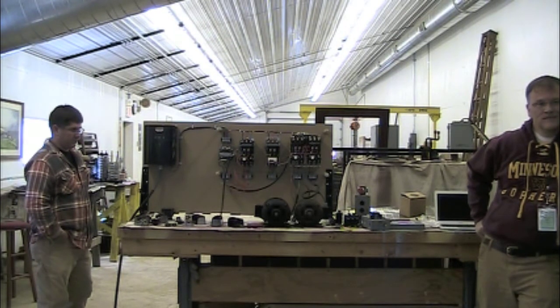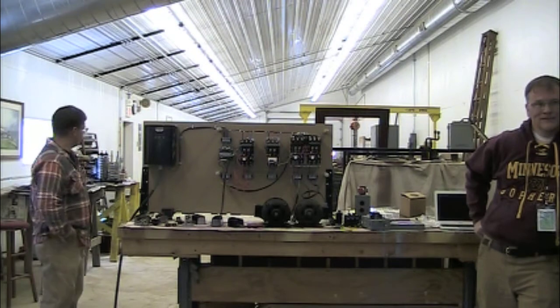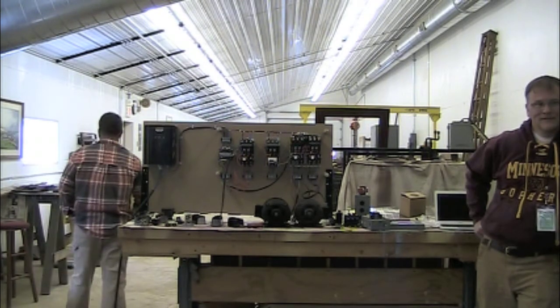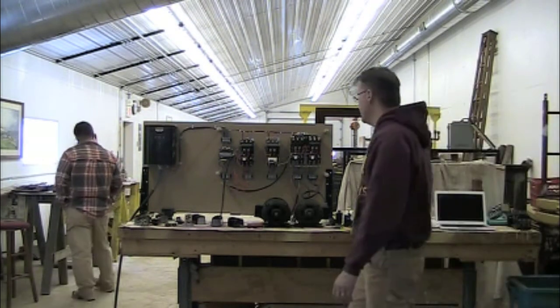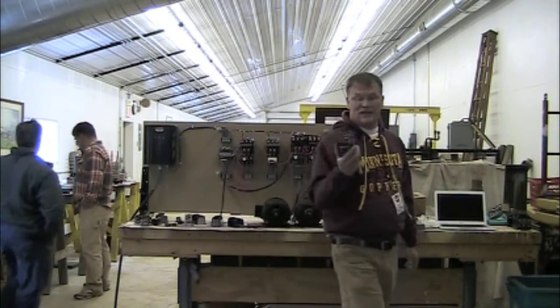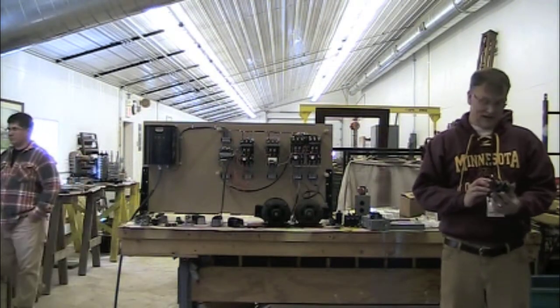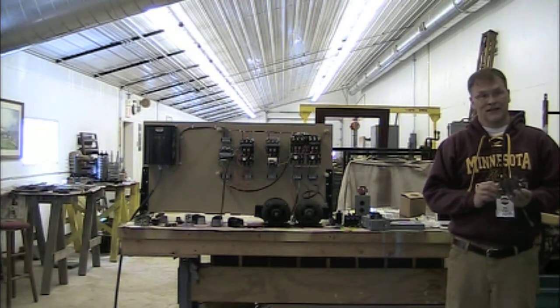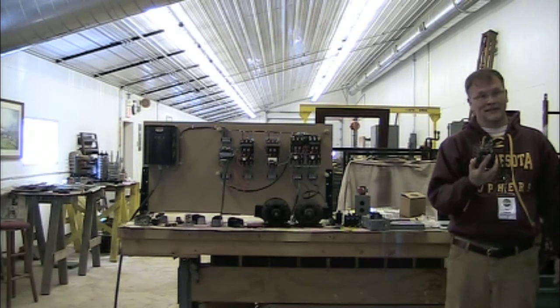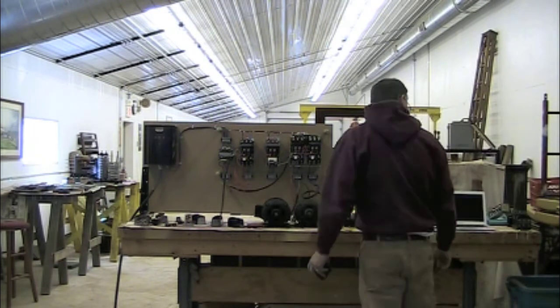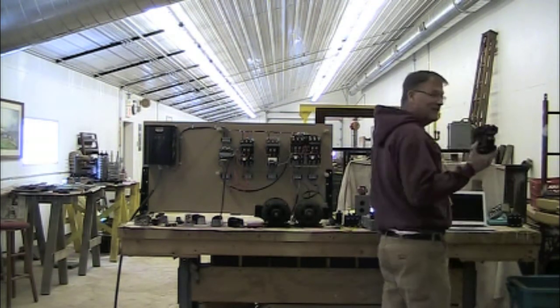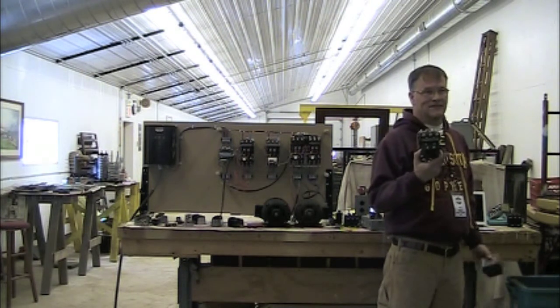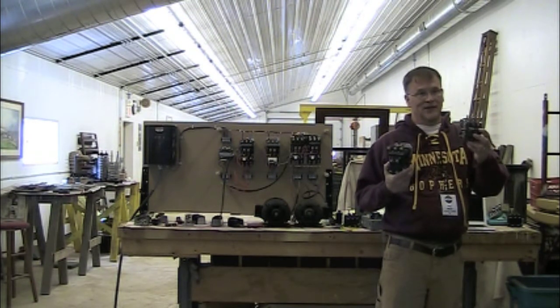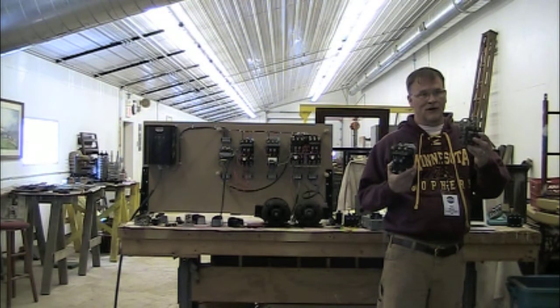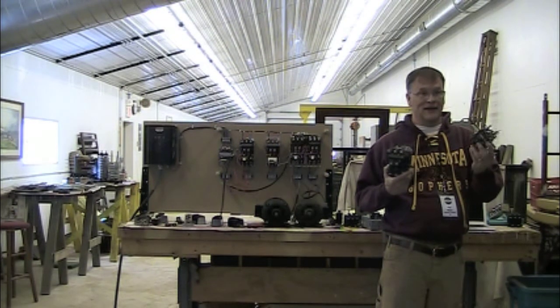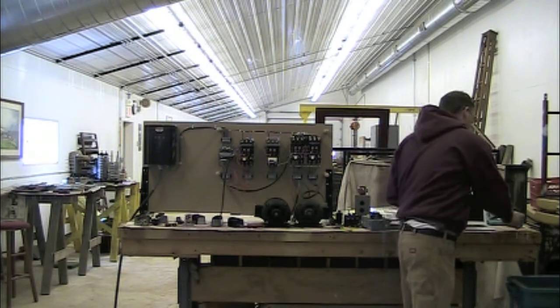So when we're looking at a box of old starters, we should be able to tell whether it's just a 2-wire or whether it's a 3-wire. Well, like this one, Doug pulled this out of the stuff that he was selling. This is a definite purpose contactor. So all that is basically this piece of a starter. This is designed to be fully controlled by something else. There's no overload or anything on it. There's no auxiliary contacts. You can sometimes buy them to go on there.